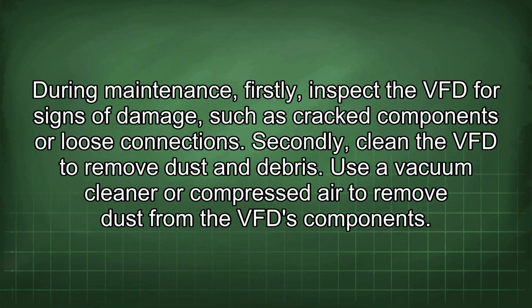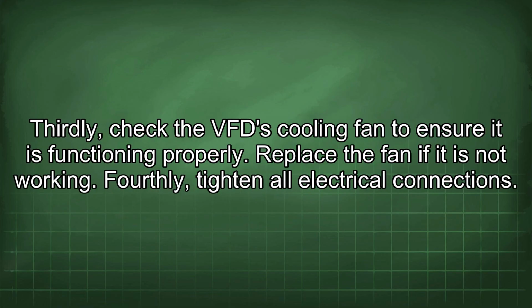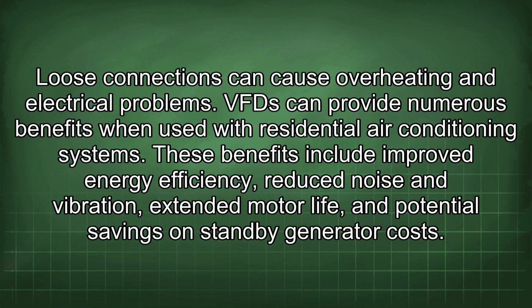During maintenance, firstly inspect the VFD for signs of damage, such as cracked components or loose connections. Secondly, clean the VFD to remove dust and debris. Use a vacuum cleaner or compressed air to remove dust from the VFD components. Thirdly, check the VFD cooling fan to ensure it is functioning properly. Replace the fan if it is not working. Fourthly, tighten all electrical connections. Loose connections can cause overheating and electrical problems.